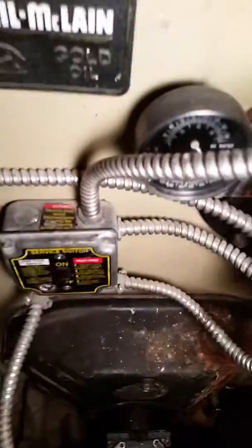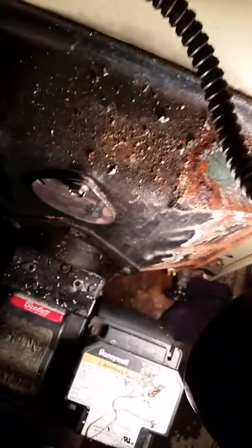The expansion tank drips straight down to the concrete. Among other things, there's also the leak at the inlet to the tankless coil right there — that completely rusted-out fitting is the inlet. You can see the dripping every few seconds of water, which drips right onto this boiler cover and evaporates.